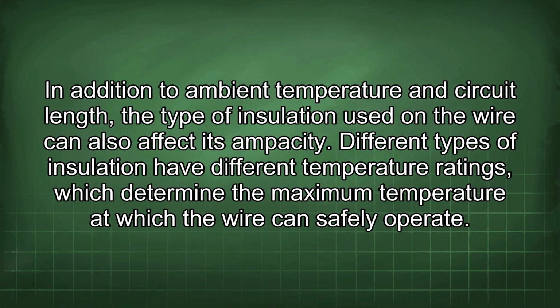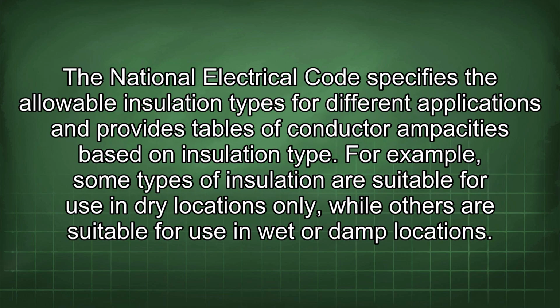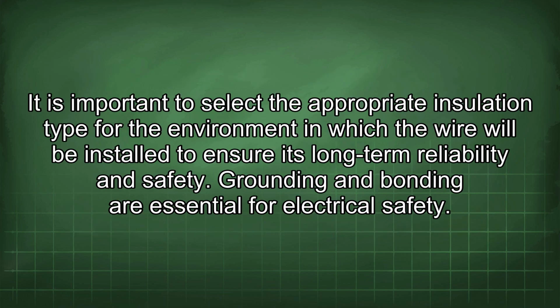In addition to ambient temperature and circuit length, the type of insulation used in the wire can also affect its ampacity. Different types of insulation have different temperature ratings, which determine the maximum temperature at which the wire can safely operate. The National Electrical Code specifies the allowable insulation types for different applications and provides tables of conductor ampacities based on insulation type. For example, some types of insulation are suitable for use in dry locations only, while others are suitable for use in wet or damp locations. It is important to select the appropriate insulation type for the environment in which the wire will be installed to ensure its long-term reliability and safety.